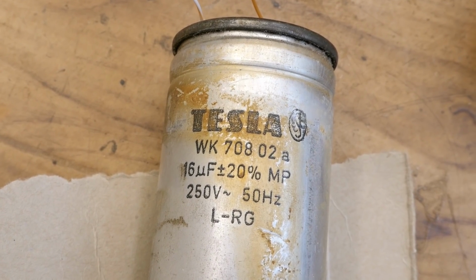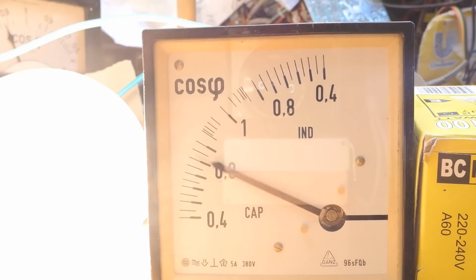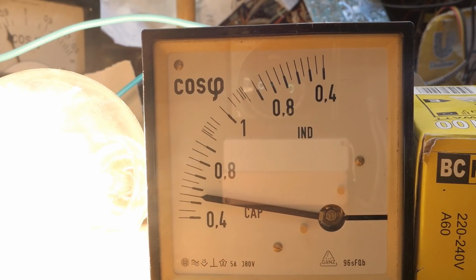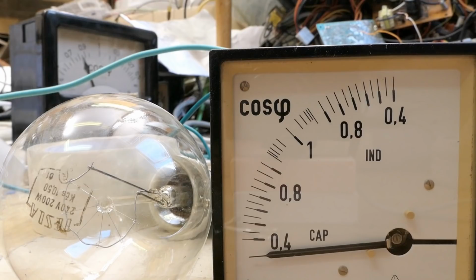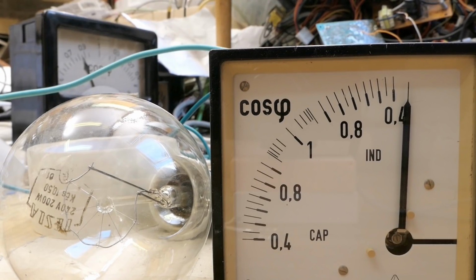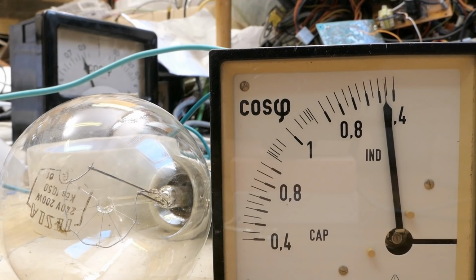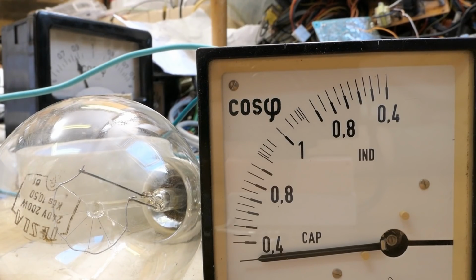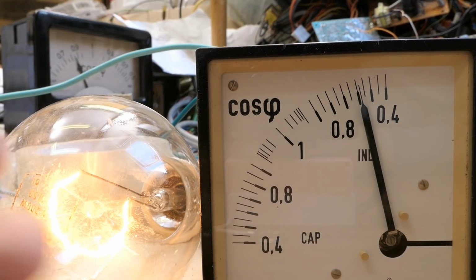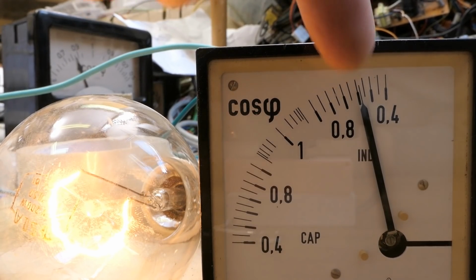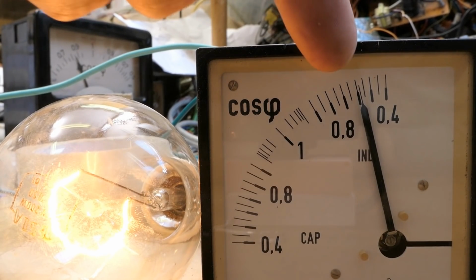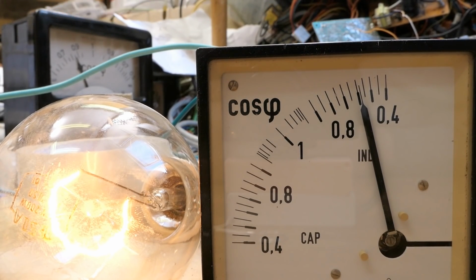And now a capacitor, of course. And it's on the capacitive side. And with just the inductor and no tungsten lamp, it goes over a range into inductive. And the inductor in series with the lamp instead of parallel reduces the brightness of the lamp, and the power factor is partially resistive, partially inductive. So it's still on the inductive side of the scale.